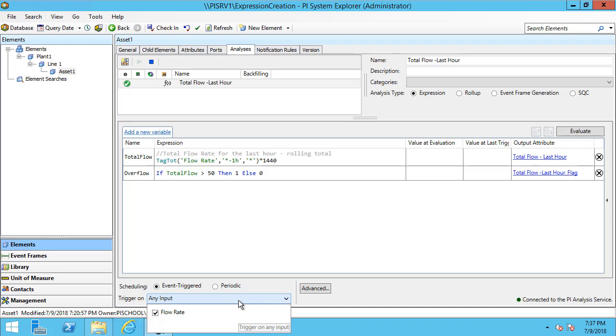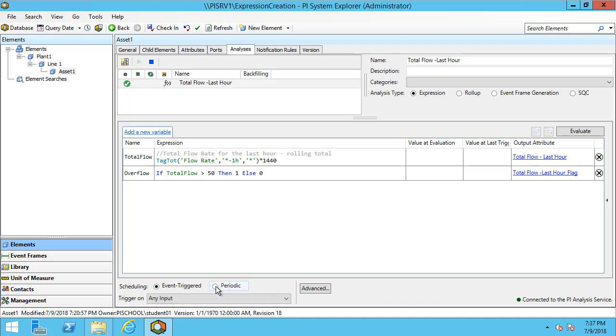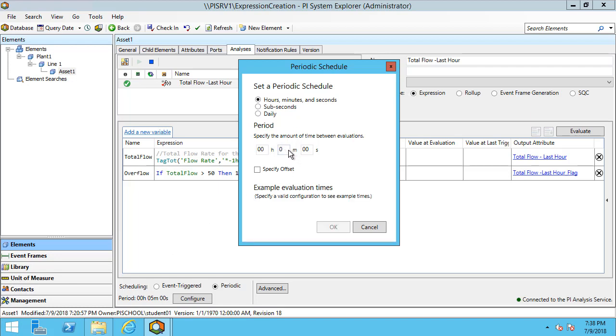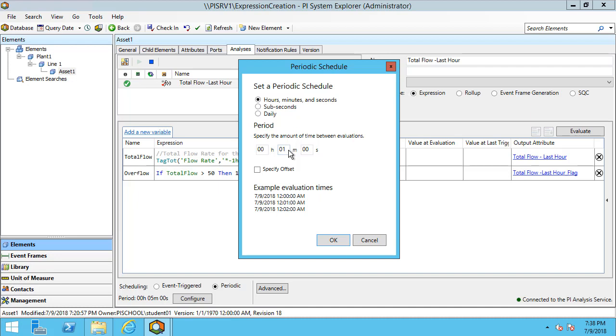Another option for scheduling is to select periodic. If I select periodic, by default, I'll have a period of five minutes. In my case, I'll configure this to be using the hours, minutes, and seconds. I would like my analysis to be run every single minute, and I would also like it to be run 30 seconds past the minute.